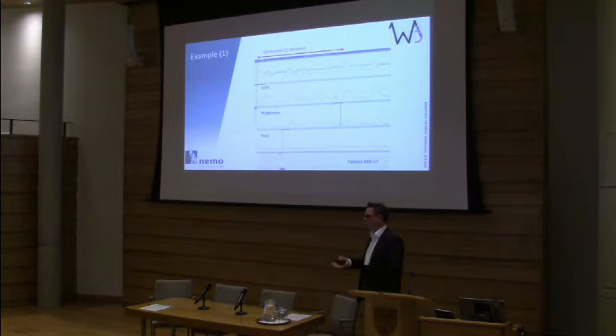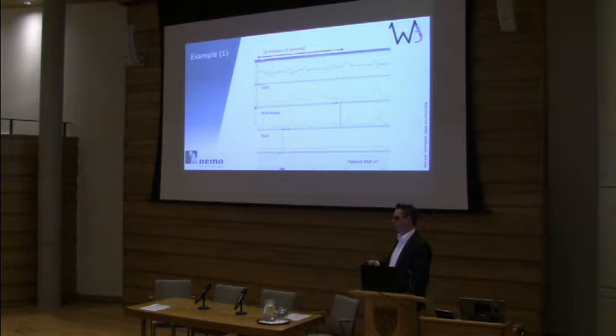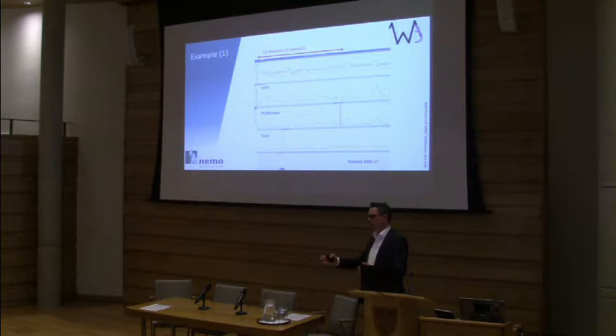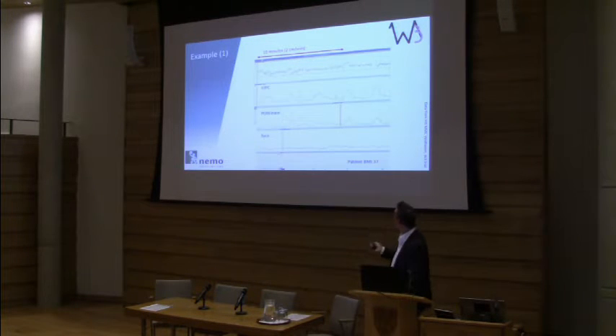Yeah, well, we're constantly improving these algorithms, but you need to keep in mind that when you produce a medical device, you have to create a file, and this file needs comparison data. So we've compared our algorithm to IUPC and to TOCO, and this has been submitted. Changing my algorithm in my hardware requires a change of my notified bodies and renewed CE marking or FDA clearance. So it's not just a matter of let's change the algorithm and do this again, because it's the heart of my system, which is considered a significant change to the technical file.